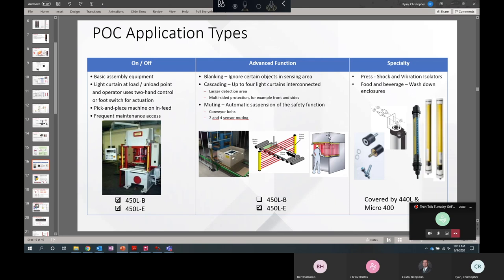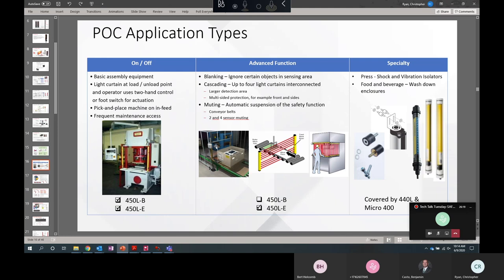So we're going to be talking about these three advanced applications from right to left. This shows cascading, that is these light curtains bending around the corner connected in series to each other. That's cascading. Blanking is where we blank beams anywhere in there. There's a few different forms of that. We'll be talking about that next. And then muting. This is typically on a conveyor with additional muting sensors to detect the difference between material that needs to pass through and a human. So we're going to start with cascading.